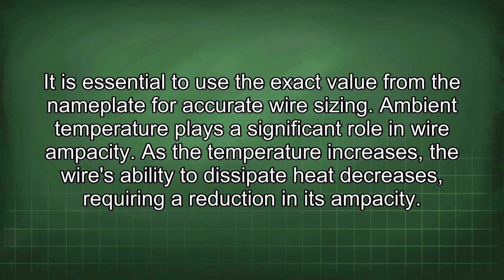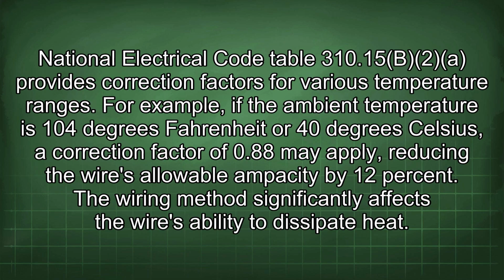Ambient temperature plays a significant role in wire ampacity. As the temperature increases, the wire's ability to dissipate heat decreases, requiring a reduction in its ampacity. National Electrical Code Table 310.15(B)(2) provides correction factors for various temperature ranges. For example, if the ambient temperature is 104 degrees Fahrenheit or 40 degrees Celsius, a correction factor of 0.88 may apply, reducing the wire's allowable ampacity by 12%.